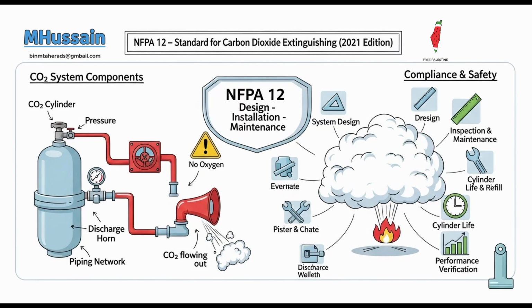During any maintenance or testing procedures on the system or within the protected space, the CO2 system must be locked out. Must be. Or the protected space and any potentially affected adjacent spaces where CO2 could migrate must be evacuated. This isn't a suggestion, it's a non-negotiable step to prevent accidental discharge. No shortcuts. If, however, fire protection needs to be maintained during this lockout period, perhaps due to a critical ongoing operation, then a fire watch must be assigned.